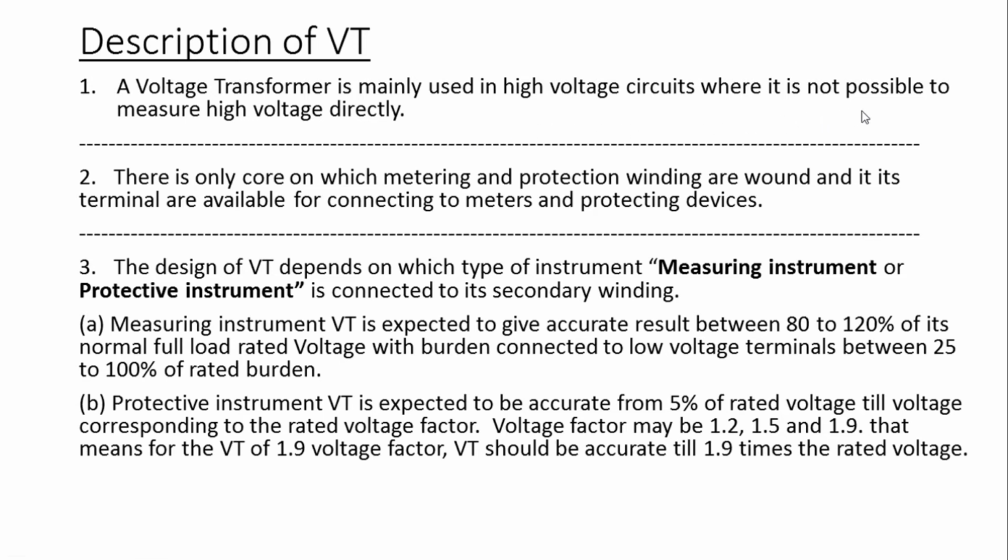A voltage transformer is mainly used in high voltage circuits where it is not possible to measure high voltage directly. There is only one core on which metering and protection windings are wound, and its terminals are available for connecting to meters and protection devices. The design of VT depends on which type of instrument, measuring instrument or protective instrument, is connected to its secondary winding.